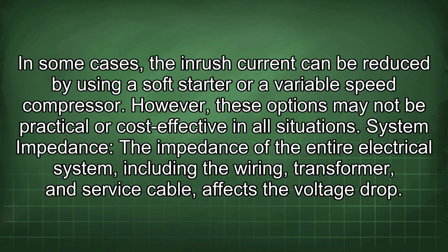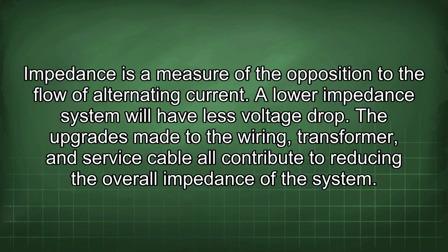System impedance. The impedance of the entire electrical system, including the wiring, transformer, and service cable, affects the voltage drop. Impedance is a measure of the opposition to the flow of alternating current. A lower impedance system will have less voltage drop. The upgrades made to the wiring, transformer, and service cable all contribute to reducing the overall impedance of the system.